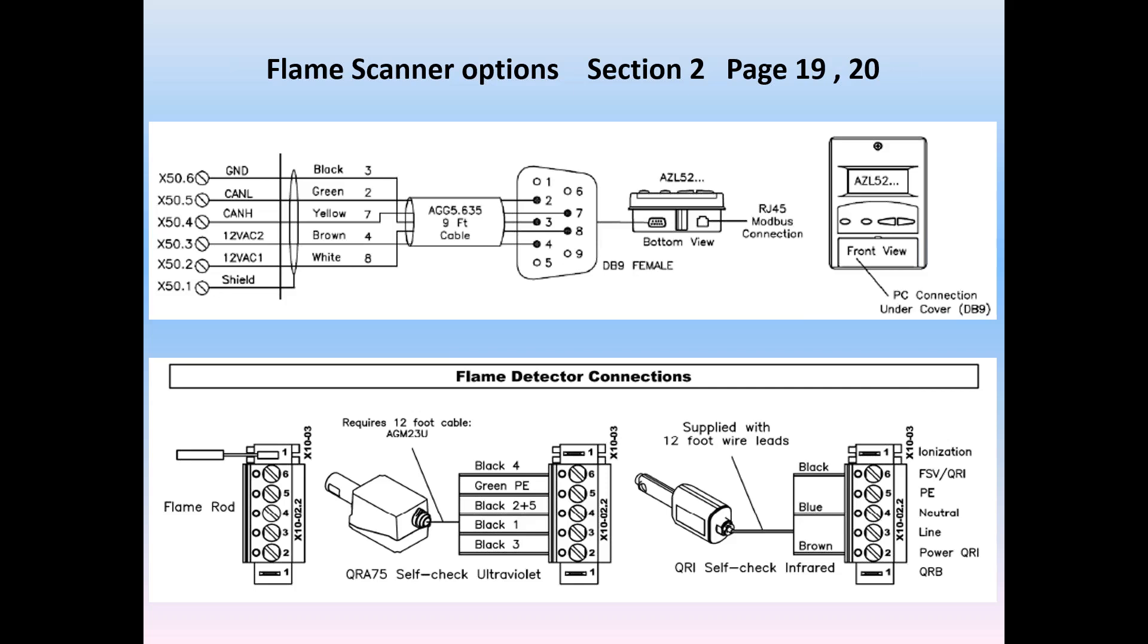Second detail on this slide is for flame detection, which could be one of any of three devices: a simple flame rod, a UV self-check scanner, or an infrared also self-check scanner. The scanner terminals have many options throughout the world. In Canada, US, Mexico, Central and South America, options are shown here. Note that the plug X10-02.2 pins start with pin number 2 instead of 1. This is most widely used on the infrared QRI scanner, which is shown.